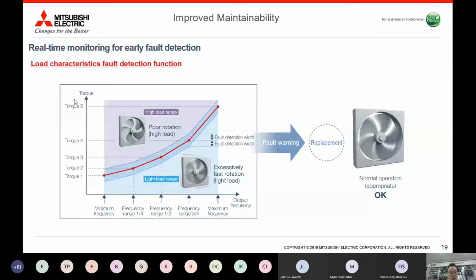This shows the torque versus output frequency curve. By default, there is a standard speed torque characteristic stored when no fault occurs. When a fault actually occurs, it falls outside of the bandwidth, and the inverter outputs an error, so maintenance personnel can go straight to the system to check it. Similarly, faults caused by stiff rotation of the motor shaft due to increased load, or cracks in the fan belt causing decreased load, can be detected through the motor output current.